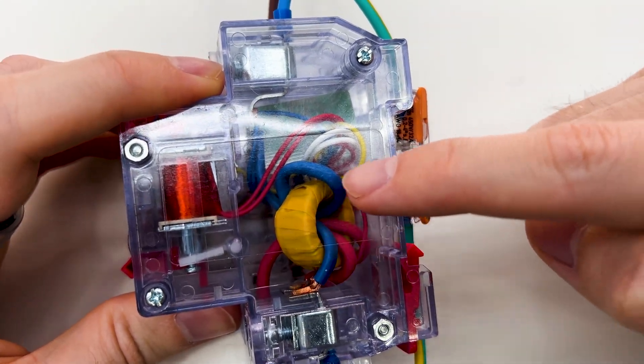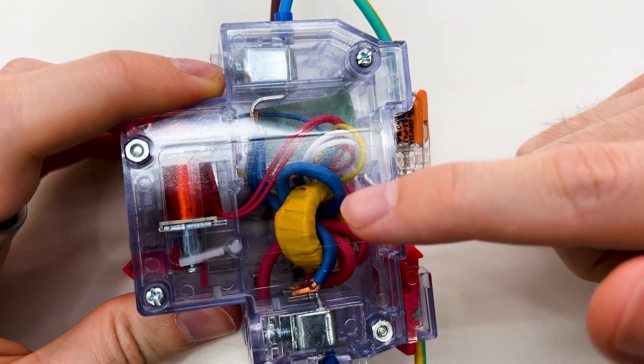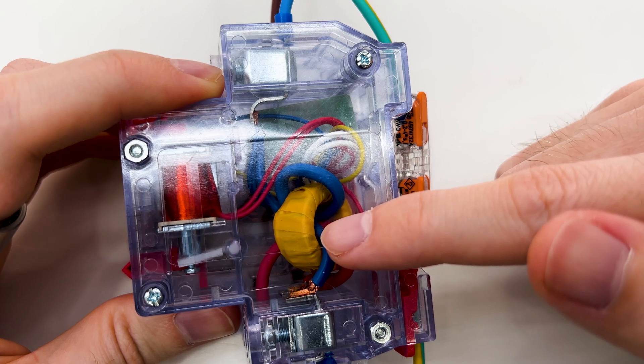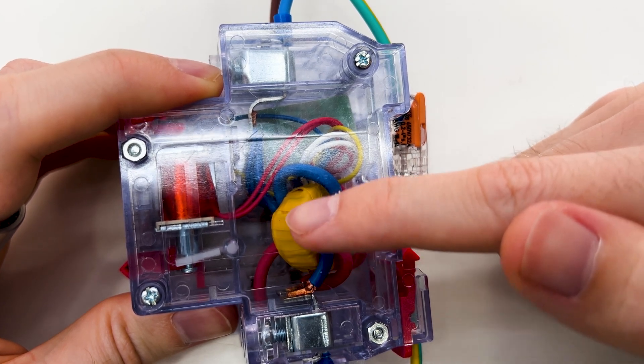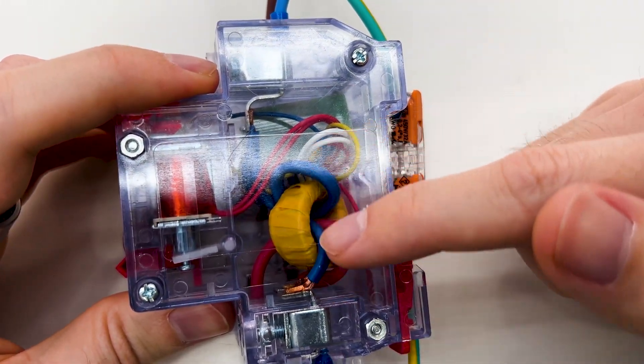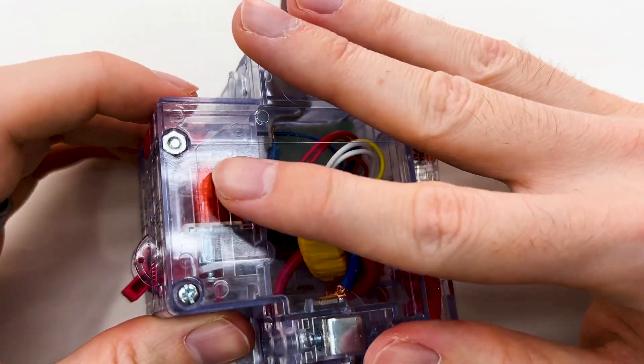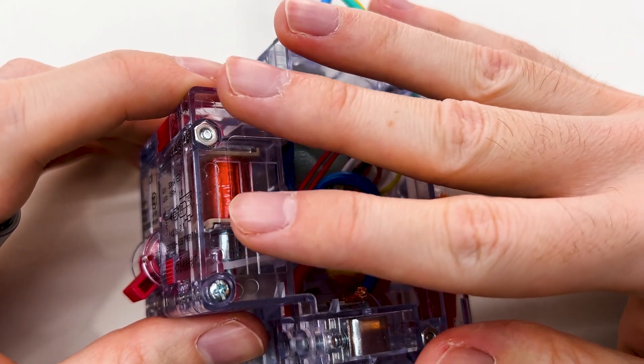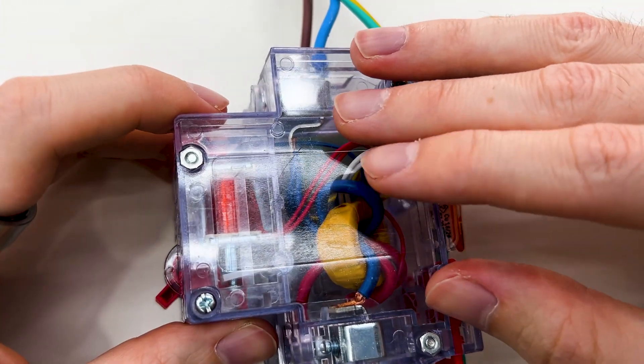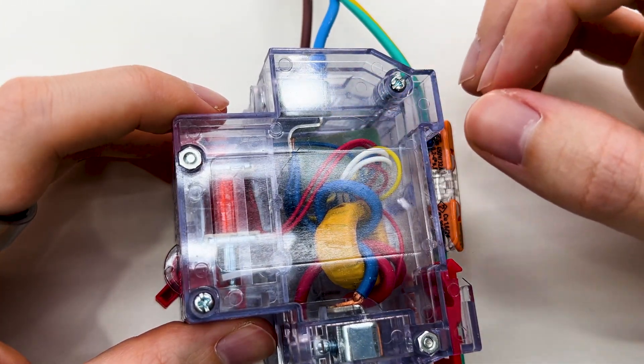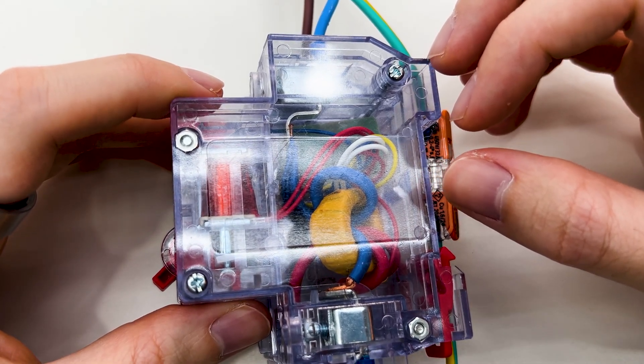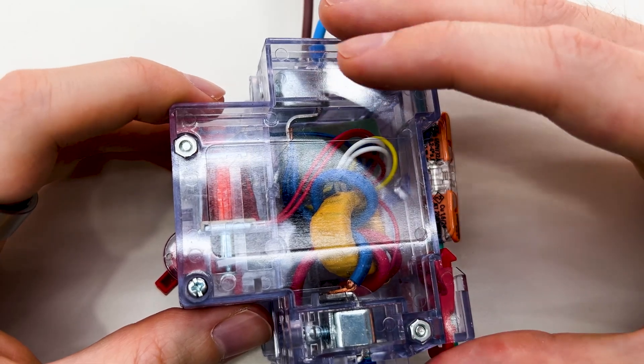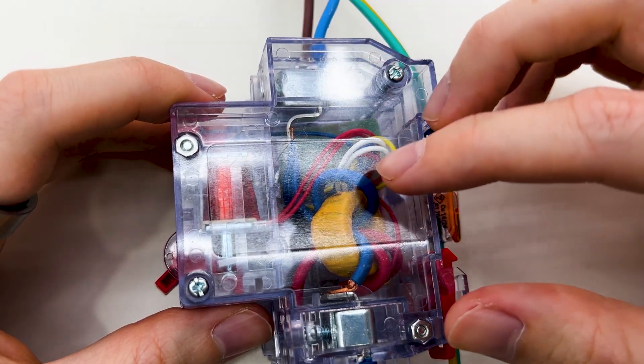This coil detects if the current going through the blue and red cables, so live and neutral cables, is the same. If the current is not matching, there is a difference between current on these two cables. And breakers have the allowed current, for example, 30 milliamps. If the current is above, it means that the current is leaking somewhere, for example, through someone's body. So if it detects that the current doesn't match on those two cables, it will trigger.